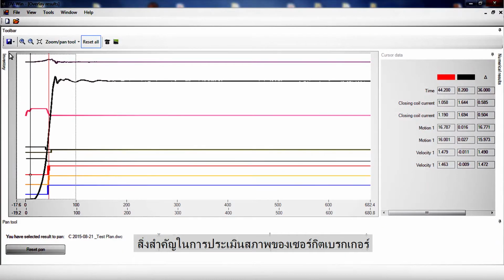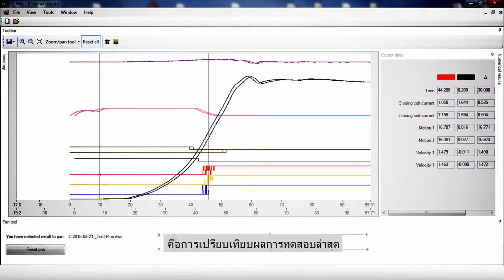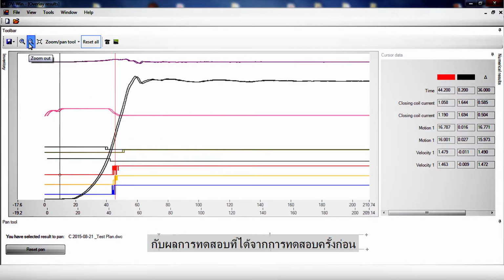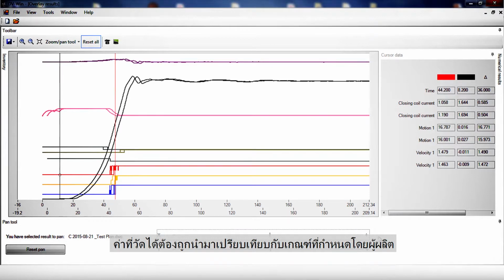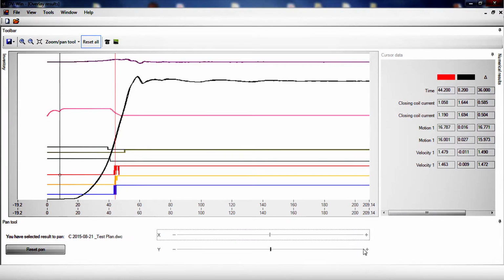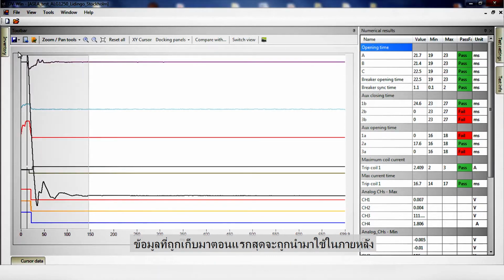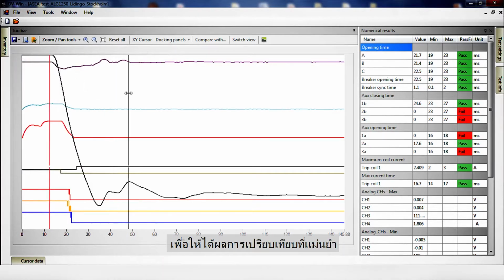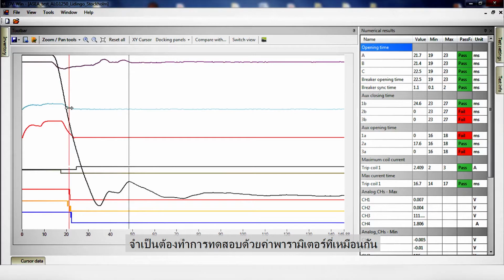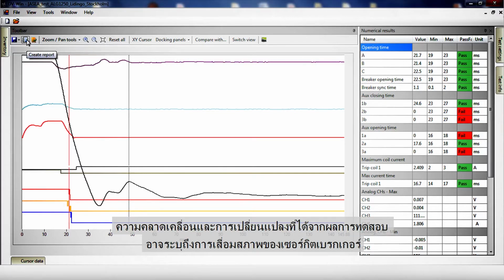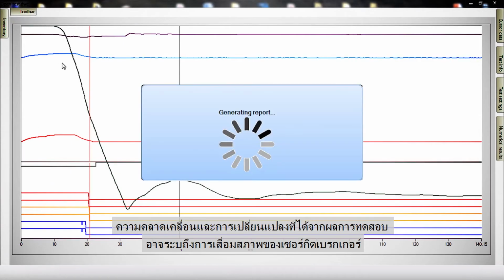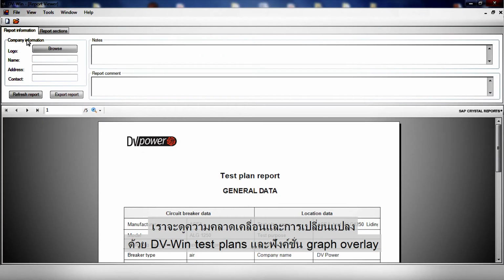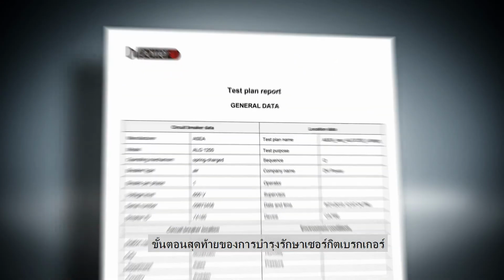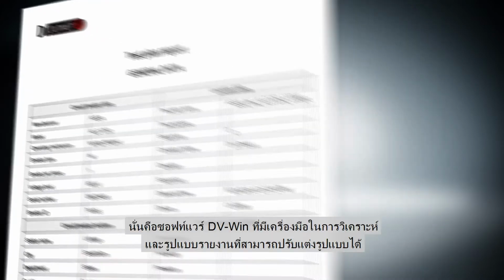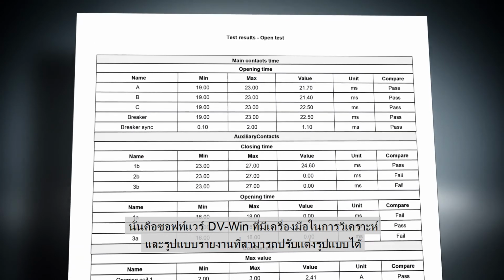An essential part of a circuit breaker condition assessment is the ability to compare the latest test results with results obtained in previous tests. Measured values are compared with limits specified by the manufacturer. The obtained fingerprint can be used at a later stage as a reference for subsequent measurements. In order to provide accurate comparison, tests need to be performed using identical test parameters. Any deviation and change in test results may indicate circuit breaker condition deterioration. This ability is supported by DV-Win test plans and the graph overlay feature. The final stage of the circuit breaker maintenance process is DV-Win, providing analytical tools and customized report creation.